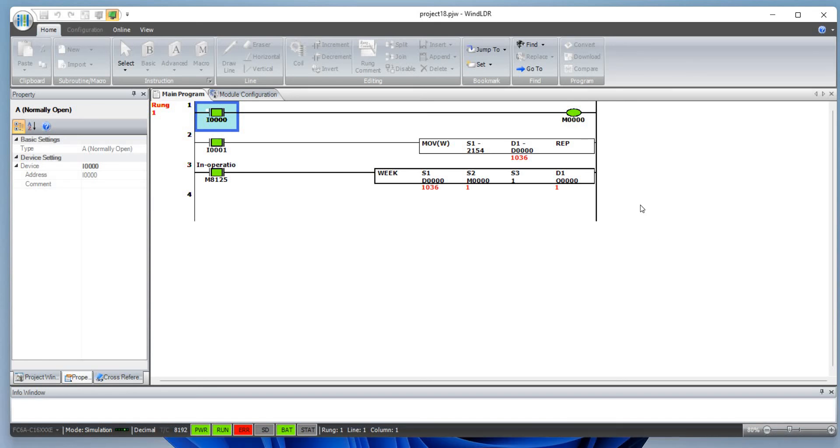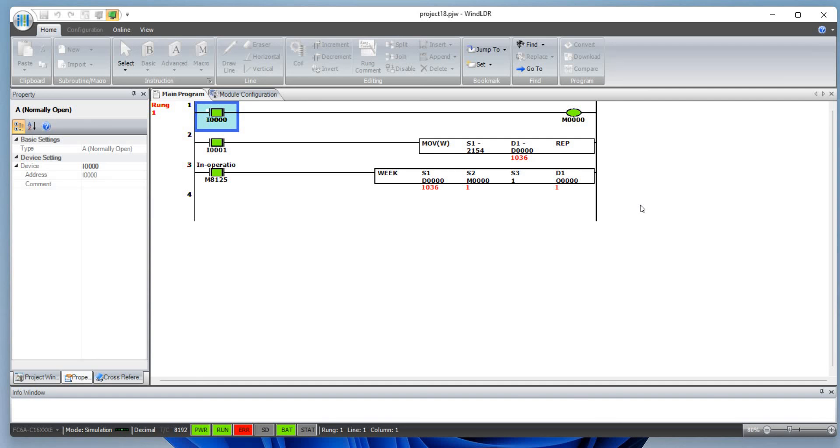The main thing here is week program instruction can be used in two different ways: one by allocating the data register. The P ranges from P1 to P20. While programming the week instructions, bit 0 to bit 6 represents Sunday to Saturday off setting, and bit 8 to bit 14 represents on setting from Sunday to Saturday. Bit 7 and bit 15 are reserved. The display numbers are shown in decimal. D0 is set for day of the week setting, D1 is set for on time, D2 is set for off time.